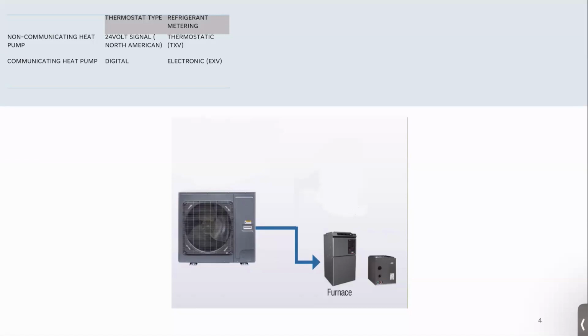In regards to how it controls its mechanisms and fans and things like that, it's speaking to the outdoor unit and the indoor unit all in tandem with a lot of algorithms built into it. Comparing the installation practices, we've done non-communicating systems all the time. As I mentioned, there's just more complexity to the communicating, so they're a little bit more challenging, and you can run into some issues with control wiring having interference. If it's up against a line voltage wire, you'll get some funky readings. We just have to work through it.